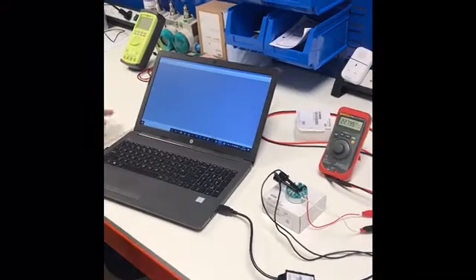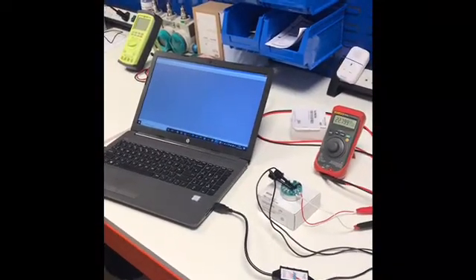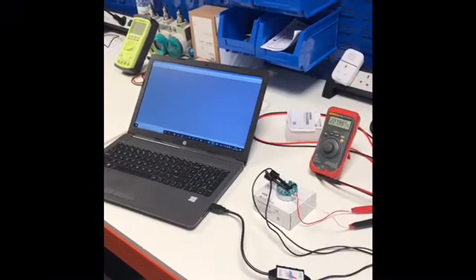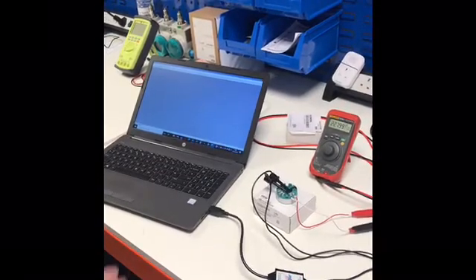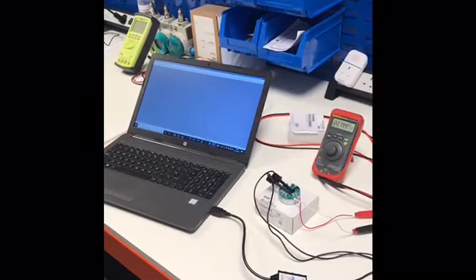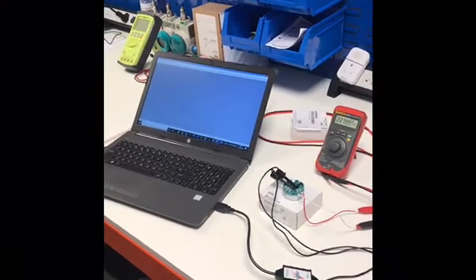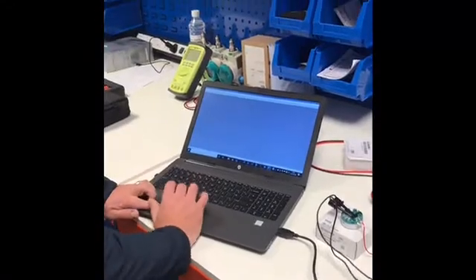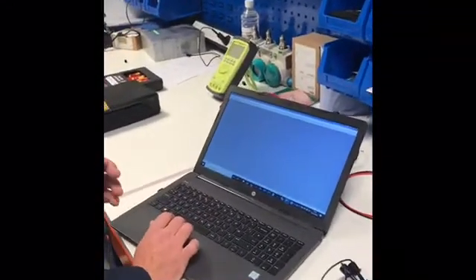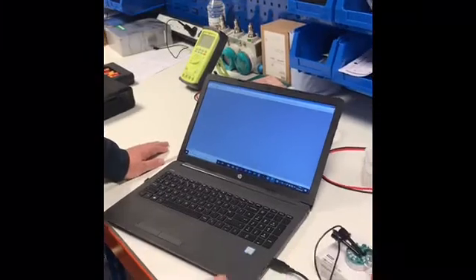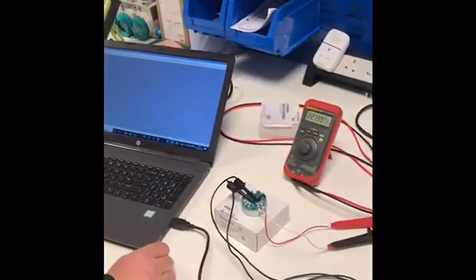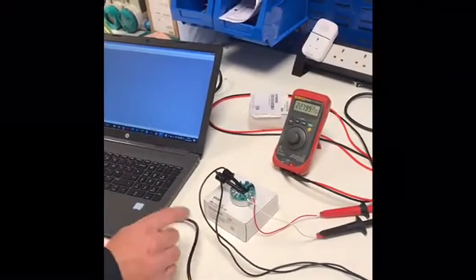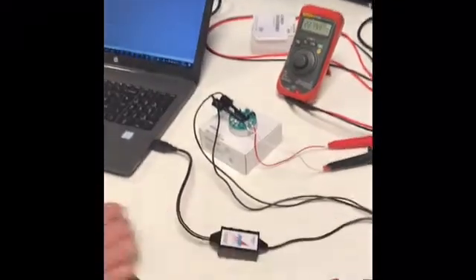Okay, so today we're just taking a look at Sitrans TH320 temperature transmitter and the basic setup and configuration using Siemens Process Device Manager, which is this application that we've got open here. To connect up to the transmitter, you have to have it loop supplied with 24 volts, you need to have a HART modem, and that has to be connected to the device on the test connections.